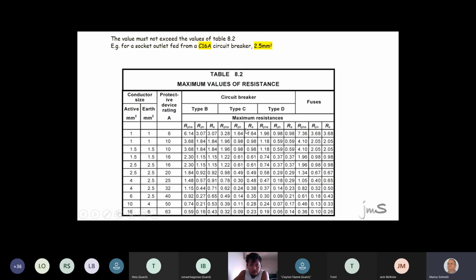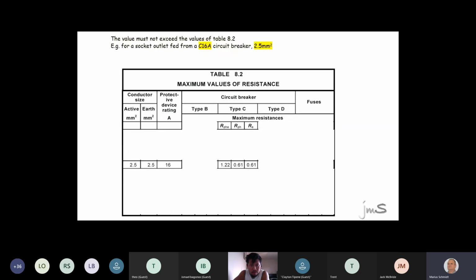Now look where my mouse is. Resistance of the earth, resistance of the phase and earth. They did it on purpose. I'm going to sneeze now. And if I sneeze, it tells you this is freaking important. Now, I'm going to do some magic there, so you can focus on one point only. You all agree it's a 2.5 cable. Can you all see 2.5 over there? You all see that? Right. Can you all see the 16 amp breaker? See there? C16. Right. C type. What's the resistance of the earth? Maximum 0.61. That is low enough to protect that circuit so that when a fault occurs, the protection device will operate within 0.4 of a second. What's the 1.22?